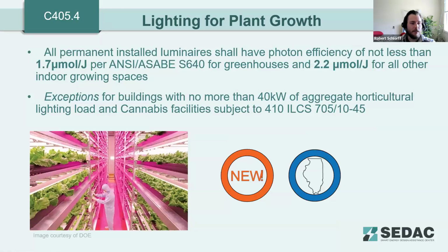Lighting for plant growth. This is an Illinois amendment to the code. All permanently installed luminaires for plant growth shall have photon efficiency of not less than 1.7 micromoles per joule per ANSI and ASABE S640 for greenhouses, and 2.2 micromoles per joule for all other indoor growing spaces. So it would depend on what the space is, if it's a greenhouse or just another indoor growing space. There is an exception listed for buildings with no more than 40 kilowatts of aggregate horticultural lighting load, and facilities subject to Illinois legislation for in-state cannabis facilities.